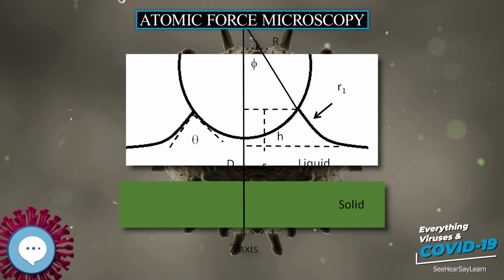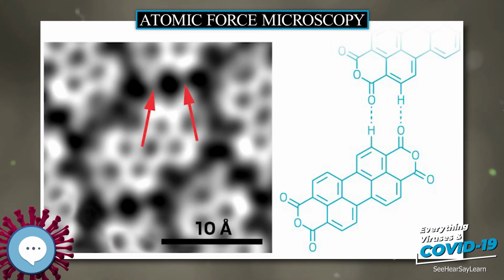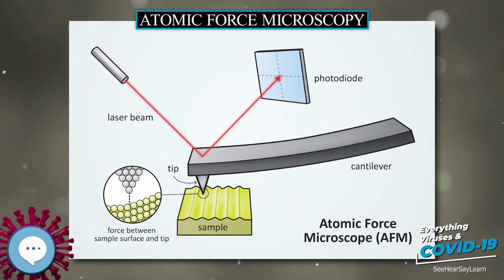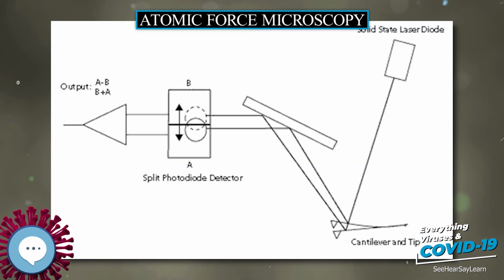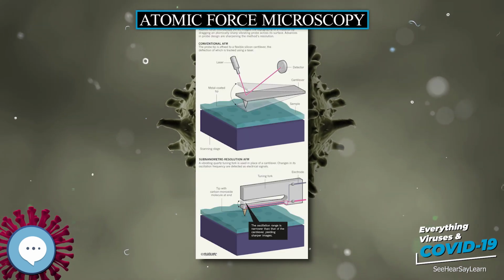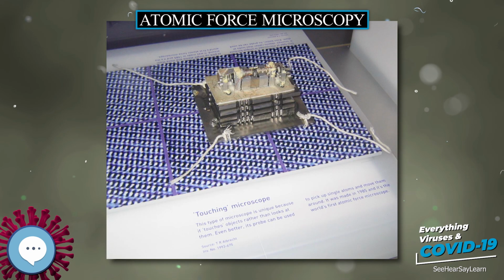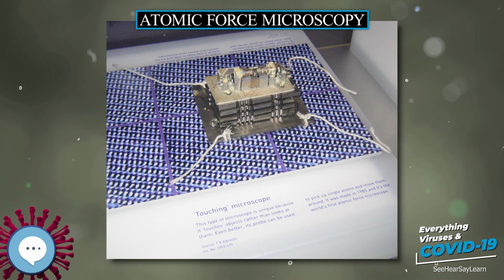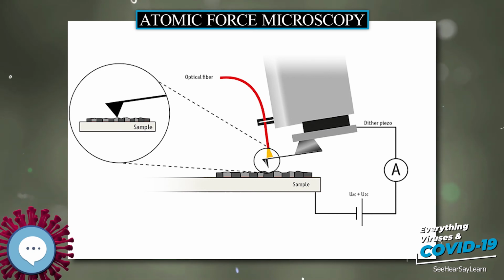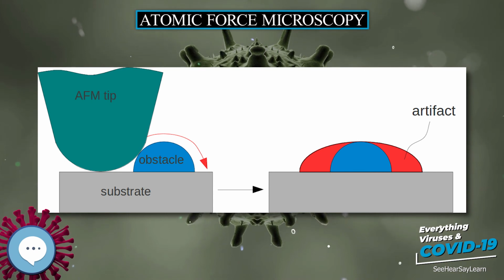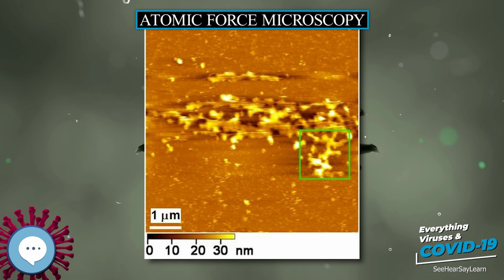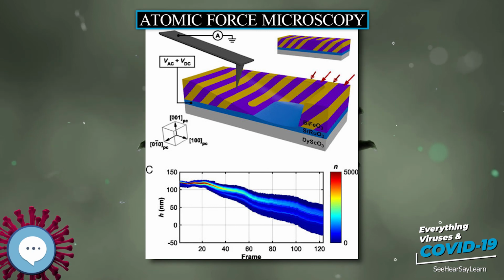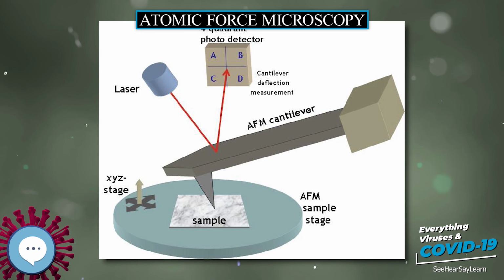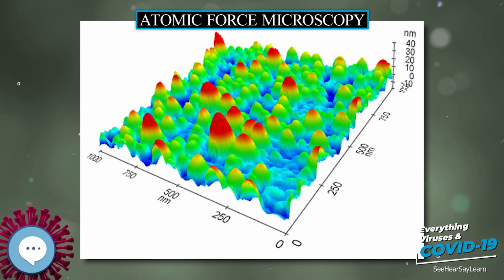Non-contact mode. In non-contact atomic force microscopy mode, the tip of the cantilever does not contact the sample surface. The cantilever is instead oscillated at either its resonant frequency, frequency modulation, or just above, amplitude modulation, where the amplitude of oscillation is typically a few nanometers, less than 10 nanometers, down to a few picometers. The van der Waals forces, which are strongest from 1 nanometer to 10 nanometers above the surface, or any other long-range force that extends above the surface, act to decrease the resonance frequency of the cantilever. This decrease in resonant frequency combined with the feedback loop system maintains a constant oscillation amplitude or frequency by adjusting the average tip-to-sample distance. Measuring the tip-to-sample distance at each x, y data point allows the scanning software to construct a topographic image of the sample surface.